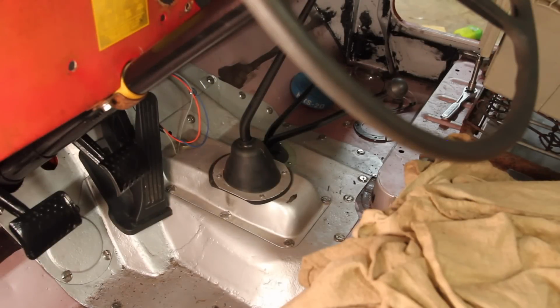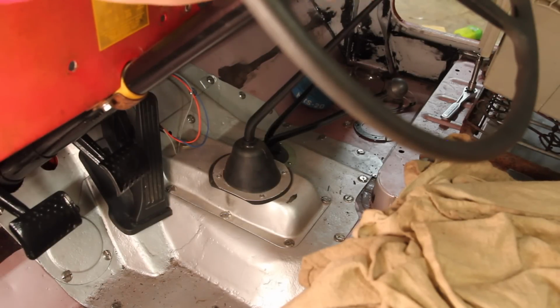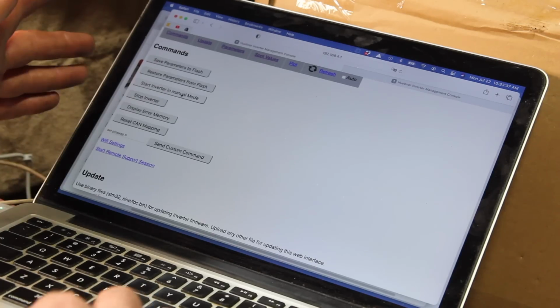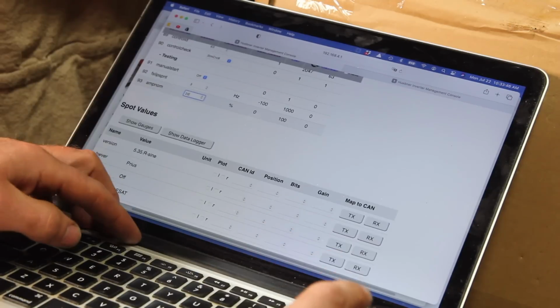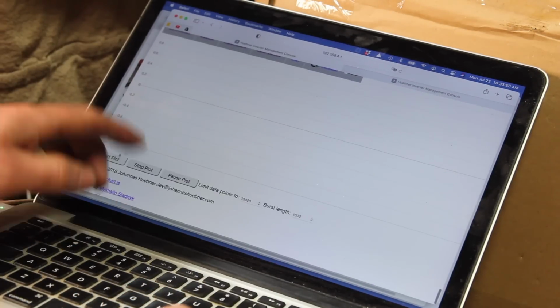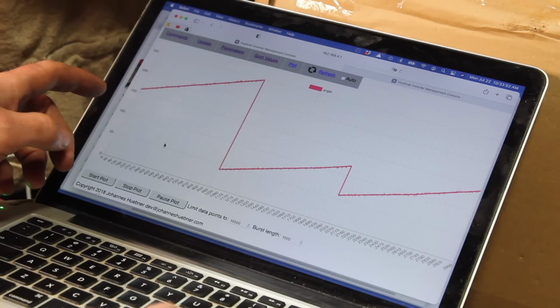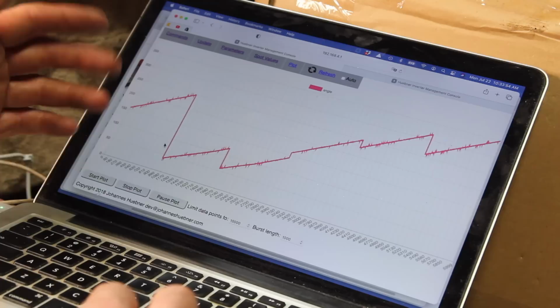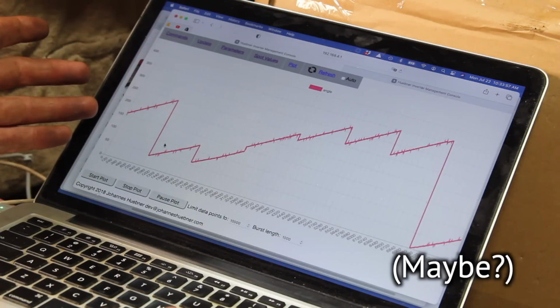So now back to the problem at hand. If we take the transmission out of gear, start our inverter in manual mode, give it 20% amp nom, and then plot our angle, what we see is the motor is in fact spinning now.